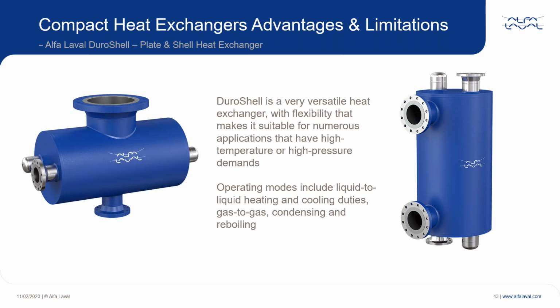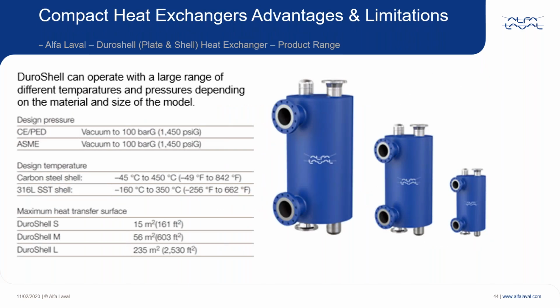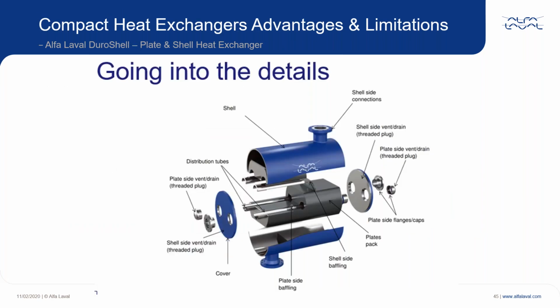Okay, the next unit is, we call it a DuroShell, but it's commonly known as a plate and shell exchanger. It's used generally in higher temperature and pressure applications. Again, it can be used in various operating modes: condenser, liquid, reboiler. We've got a relatively small range of 3 units. They can go up to 100 bar and 450 degrees C with a carbon steel shell. If we switch to a 316 shell, we're limited to 350 degrees, but we can go down to -160. And going into the details, it's made up of welded plates put into basically a welded shell.